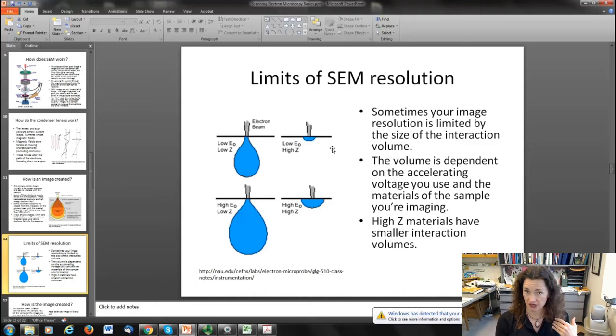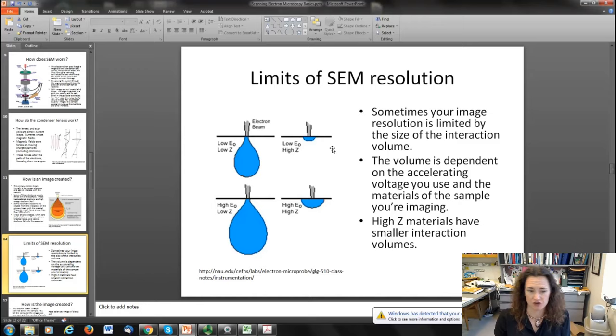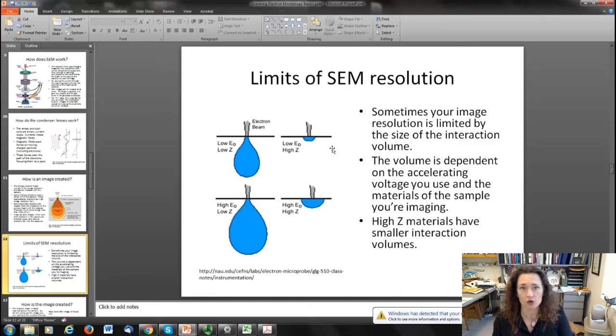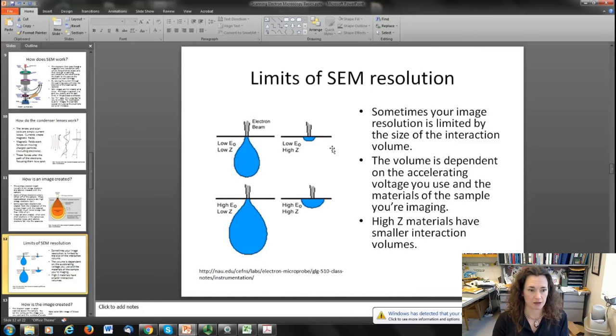This can also generate contrast. You get more scattering from a high-Z material, so if you're looking at a sample that's not uniform — say a blend of gold and carbon — the gold in the scanning electron microscopy image is going to look brighter because it reflects more electrons than the carbon, which will look darker. So you can get contrast in an image — bright versus dark — not just from topography but also based on what kind of material you're looking at.